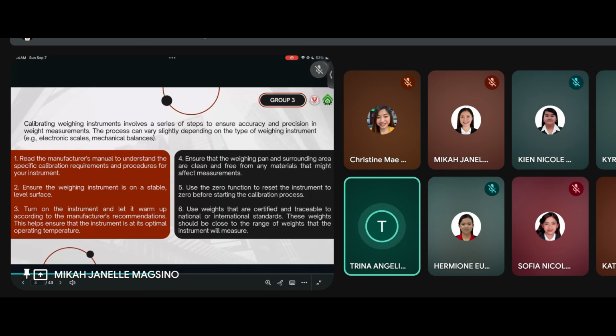The sixth is use weights that are certified and traceable to national or international standards. These weights should be close to the range of weights that the instrument will measure.